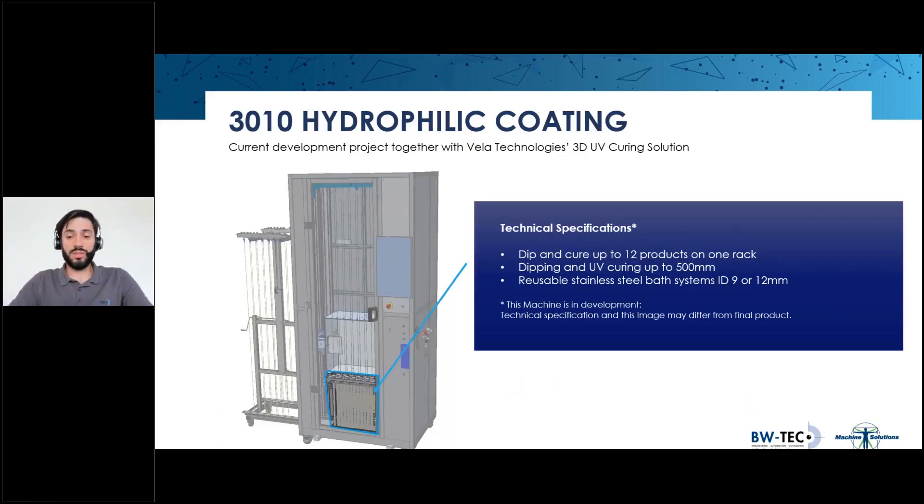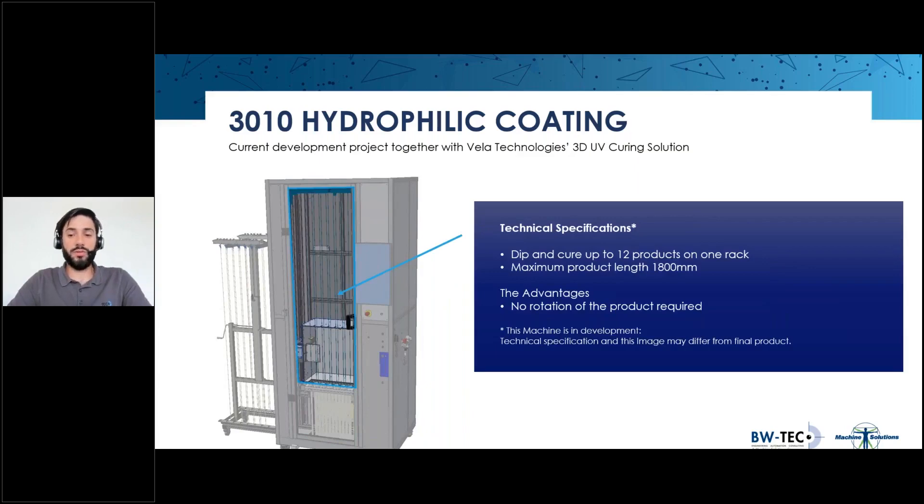Now for the news we're all here for: the next generation of coating machines are being developed together with the Vela 3D UV curing system, uniting the robust design of a BW-TEC machine with the reliability and accuracy of a Vela 3D cure. Starting with a maximum curing length of 500 millimeters while 12 products are done in one cycle, the bath design will be the same and available in 9 mm and 12 mm ID. The machine is made for catheters up to 1800 millimeters in length. Other lengths and quantities can be realized based on customer needs.